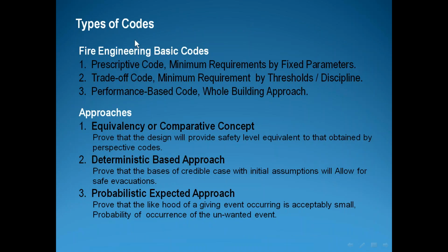We have three types internationally for the codes. We have the prescriptive codes, where the country stated the minimum requirements by fixed parameters. For example, I need to use this type of sprinklers with the amount of water to be sprayed if I have a fire inside an office. So you have fixed parameters, you can increase over it, but you cannot decrease. Otherwise, you are not code compliant.